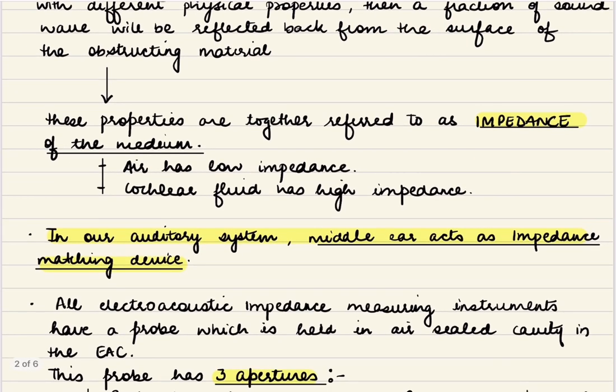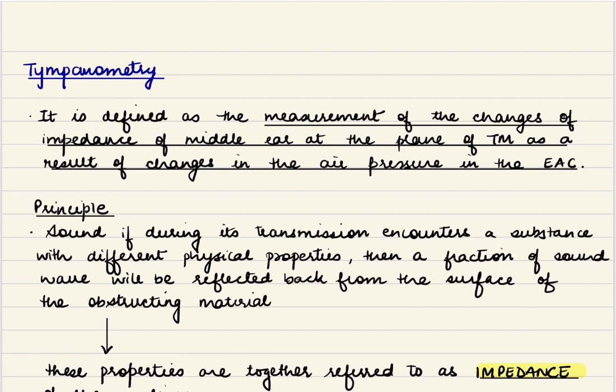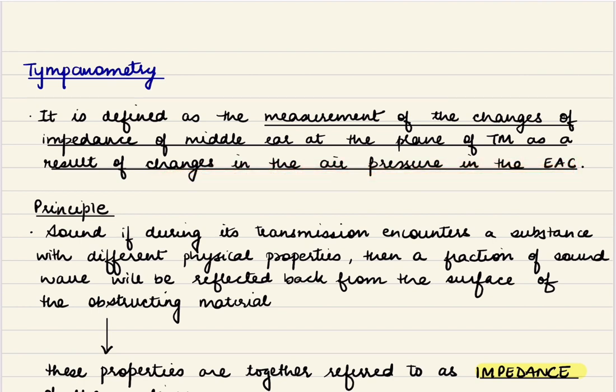Air has low impedance and cochlear fluid has high impedance. In our auditory system, sound waves travel from air to the cochlear fluid. The middle ear is the impedance matching device. Basically, what we do is change the pressure in the external auditory canal and with these changes we measure the changes in impedance of the middle ear.